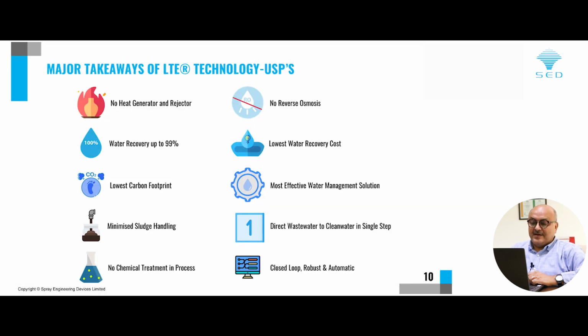So the major takeaway of the low temperature evaporator technology is there is no heat generator, no rejector. Water recovery of more than 99% is possible, depending on the in-feed TDS of the wastewater. Lowest carbon footprint, minimum sludge handling, no chemical treatment in the whole of the process, no reverse osmosis, lowest waste recovery cost, most effective water management solution, direct waste to clean water in a single step, closed loop, robust and automatic system.